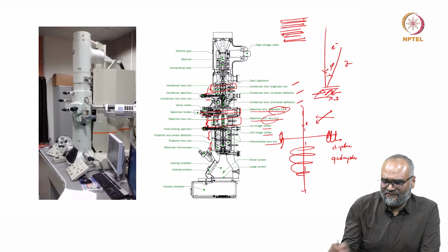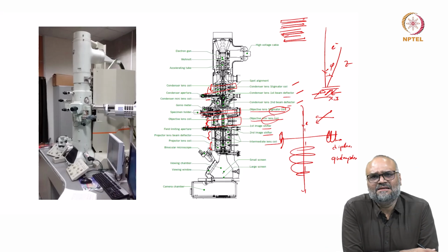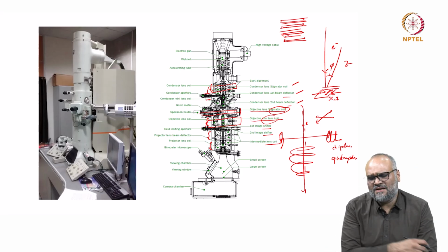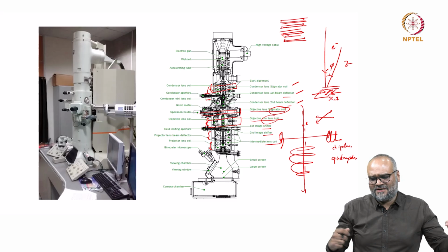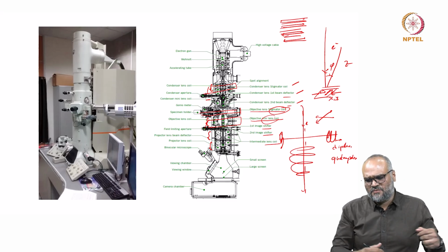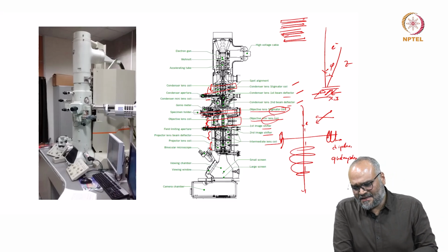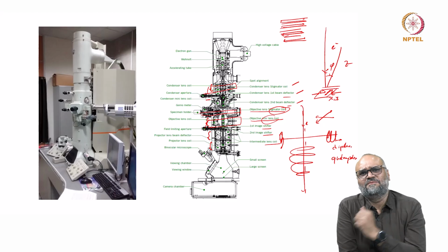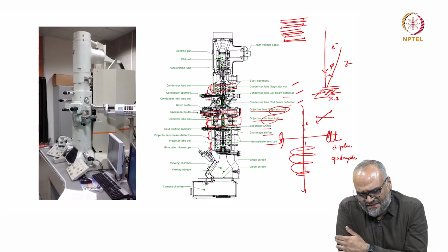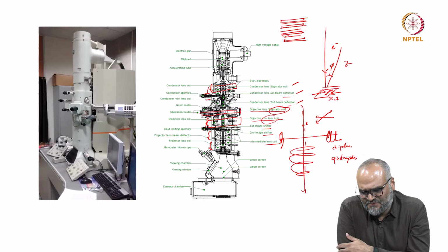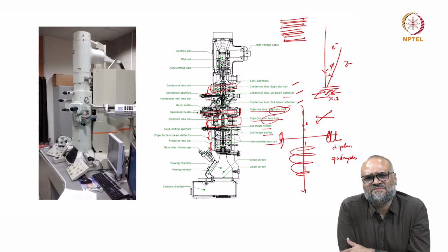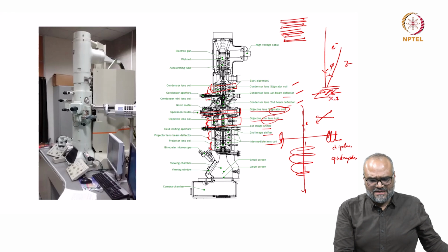Predominantly, the deflector coils are dipoles, and depending on the direction of shift you want, you might also want to introduce a quadrupole as well. The tilting can be achieved with a dipole as well. So there are different functionalities for these, and different manufacturers use different configurations, but essentially the principle is all the same.